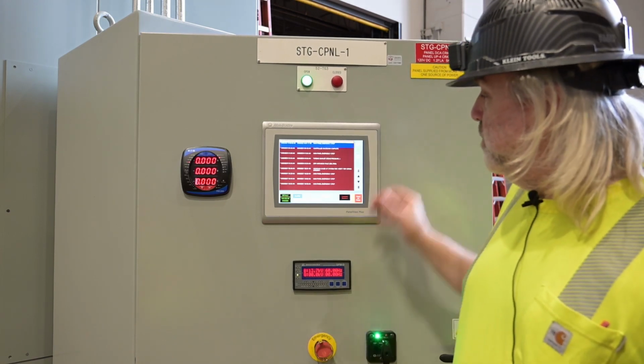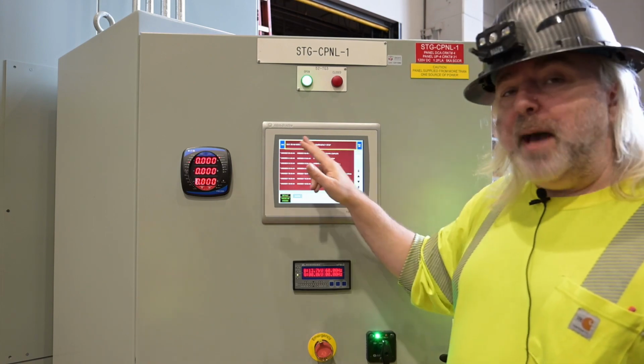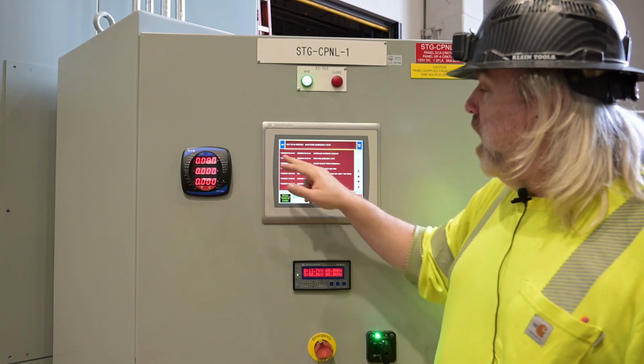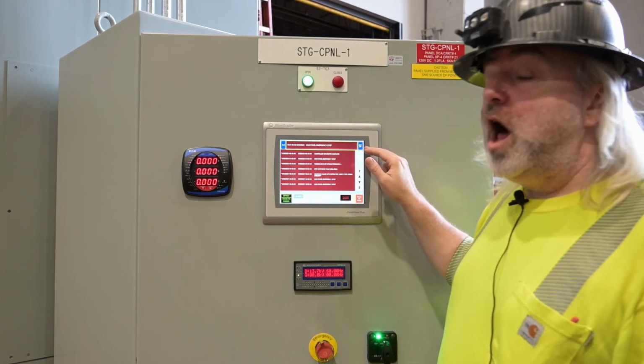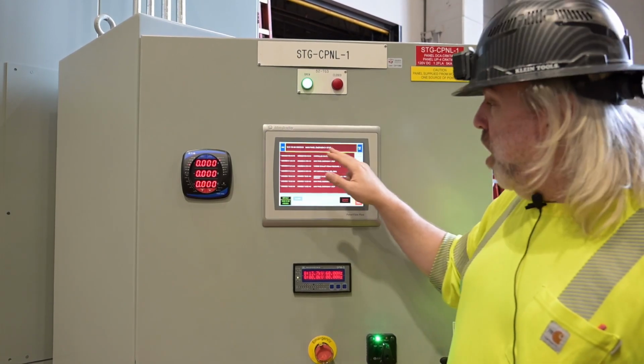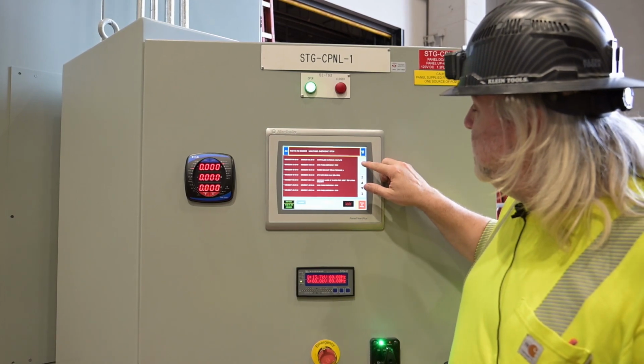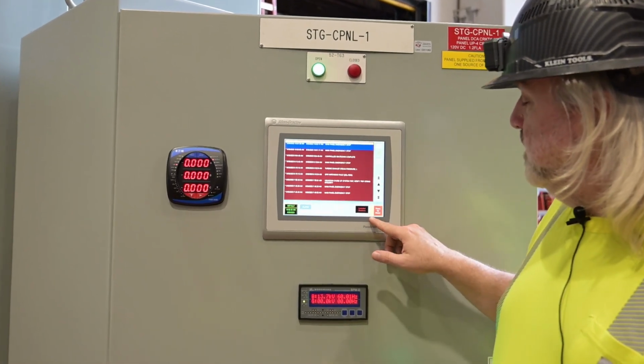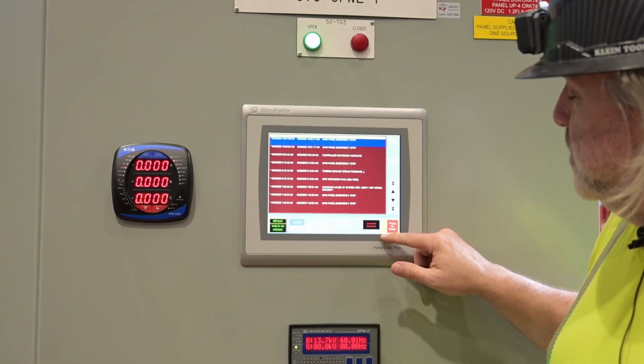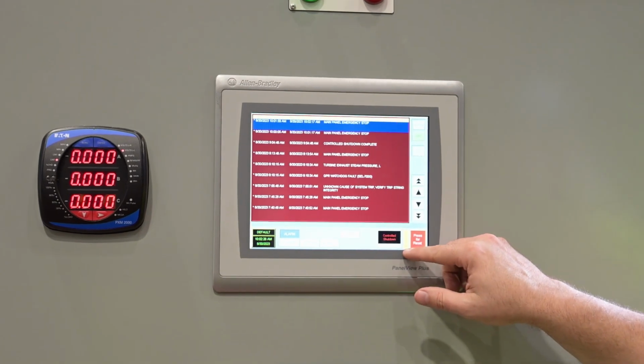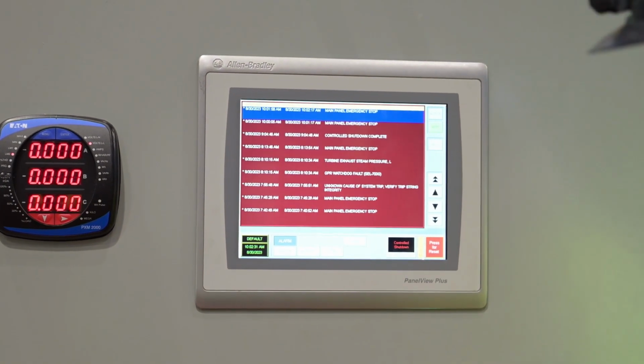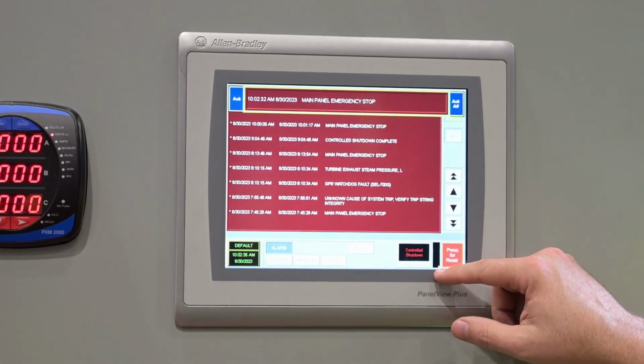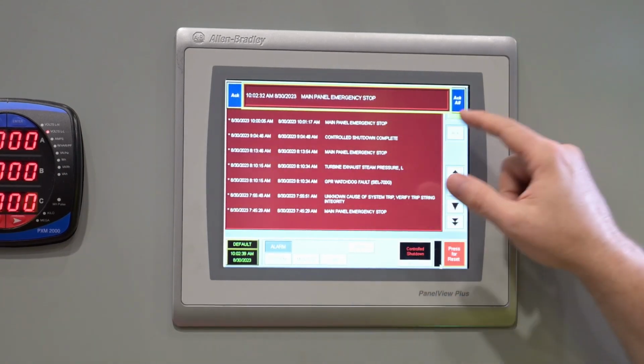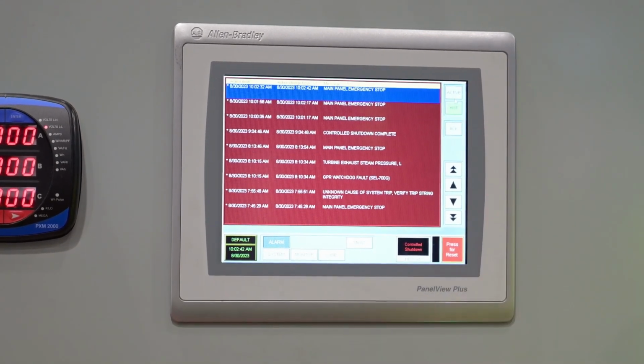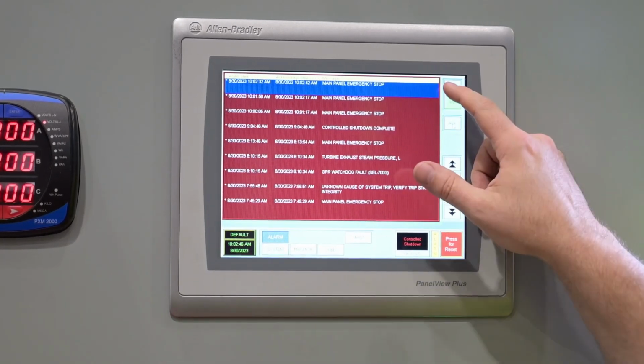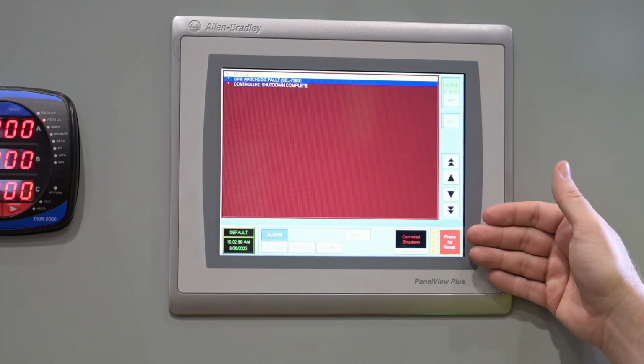If we do have an alarm, we're going to have a little pop-up. That pop-up will indicate the alarm. You can then acknowledge this alarm, or you can acknowledge all. If there are other alarms along with this alarm, that will acknowledge all of them. The other thing to do is to hit the acknowledge button. When we acknowledge, this little indicator down here shows us steady yellow means we have an active alarm. Blinking yellow means we have a new alarm that needs to be acknowledged. Again, we can acknowledge, acknowledge all, or acknowledge. So that's going over the alarm screens available to us.